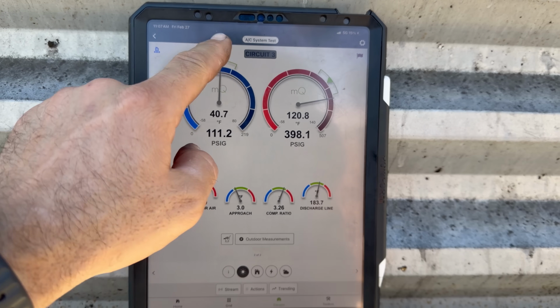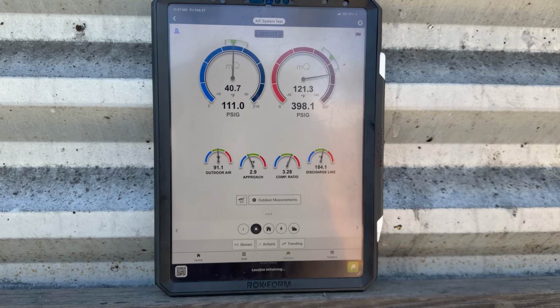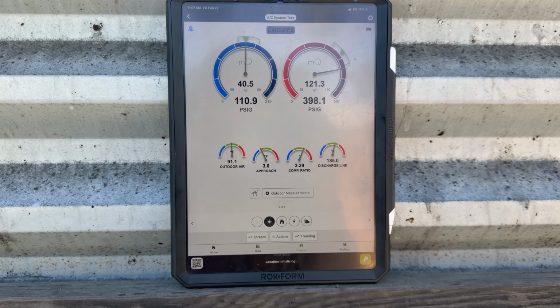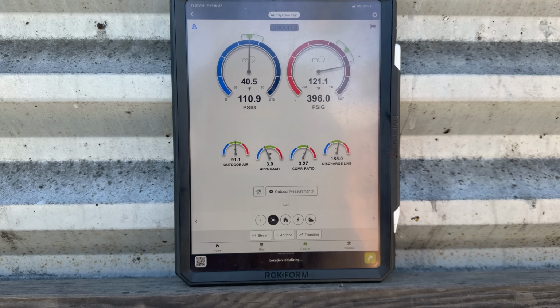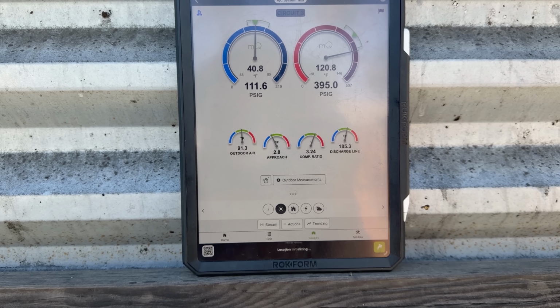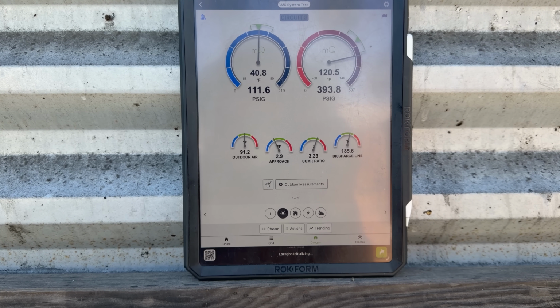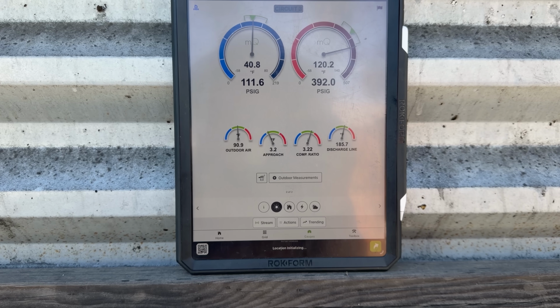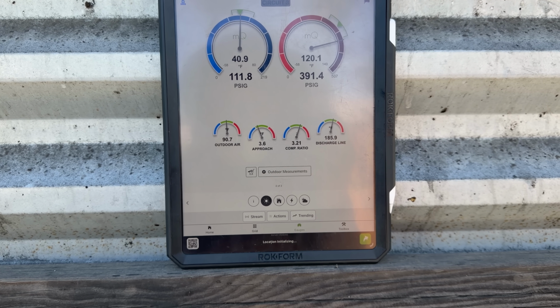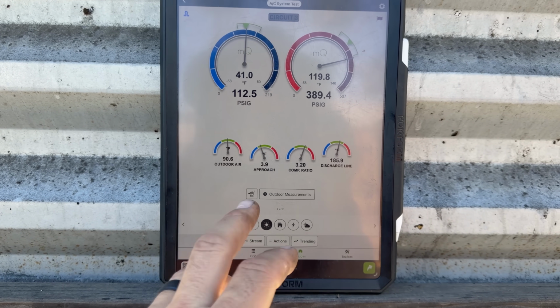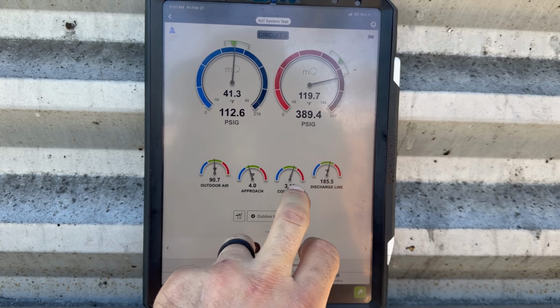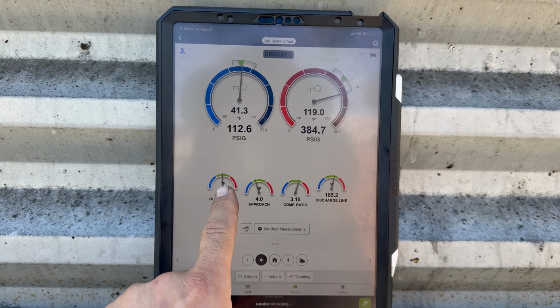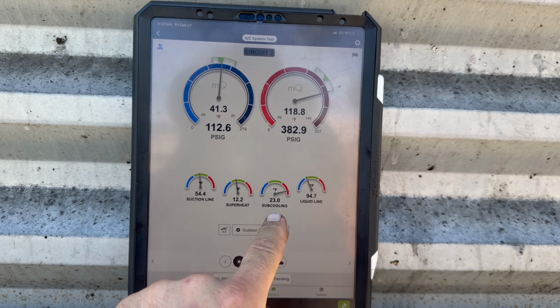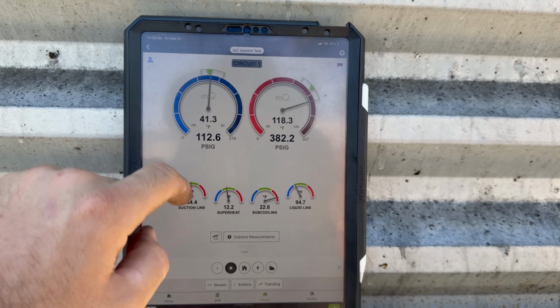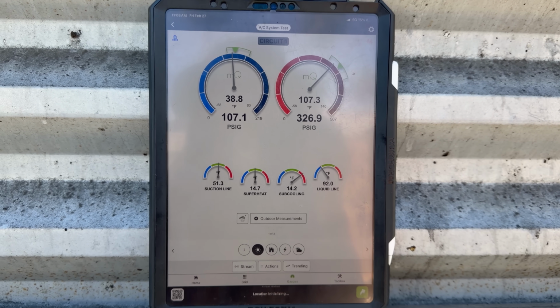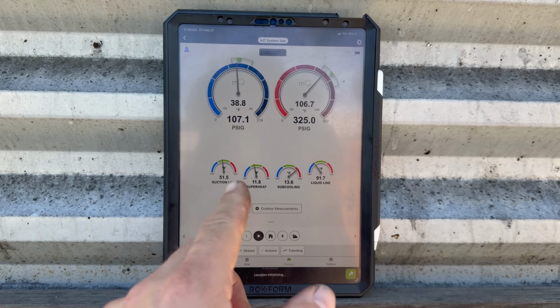But I will say too that this circuit, the third stage, if I remember right, was overcharged from the factory. And I can't remember if we actually weighed it out or if we just pulled, no, I think we pulled the whole refrigerant charge and weighed it in when we did the startup about 6 months ago or something. It was a while ago, it's hard to keep track. But that's something to keep an eye on, but it's not a red flag crazy for me as long as all the condenser fan motors are working. So we're gonna watch it for a bit, but this looks pretty darn good.